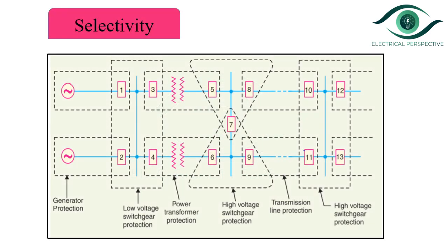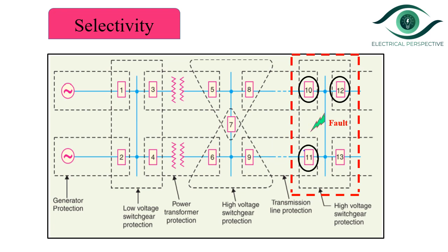Consider a system where each element is provided with its separate zone of protection. Circuit breakers are located in the connections to each power system element to disconnect only that part in case of a fault. If a fault occurs at the bus bar on the last zone — please refer the figure on the screen — then to achieve selectivity, only the circuit breakers nearest to the fault, i.e., circuit breakers 10, 11, 12, and 13, should open, isolating only the faulty section without affecting the rest of the system. Any other breaker operating to clear this fault would cause disconnection of more of the system than necessary.